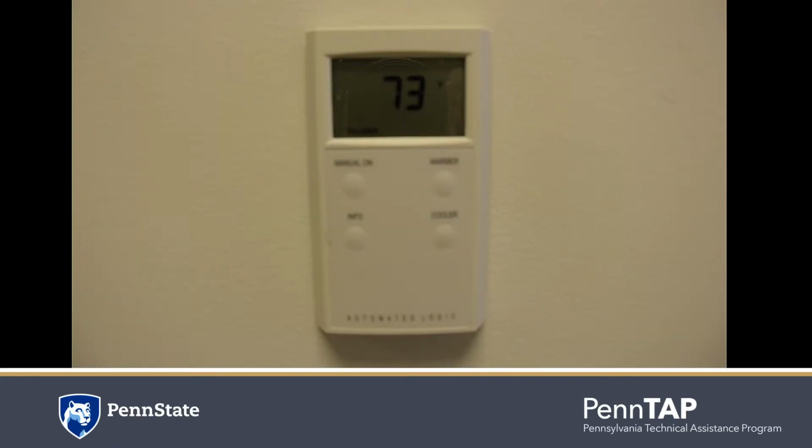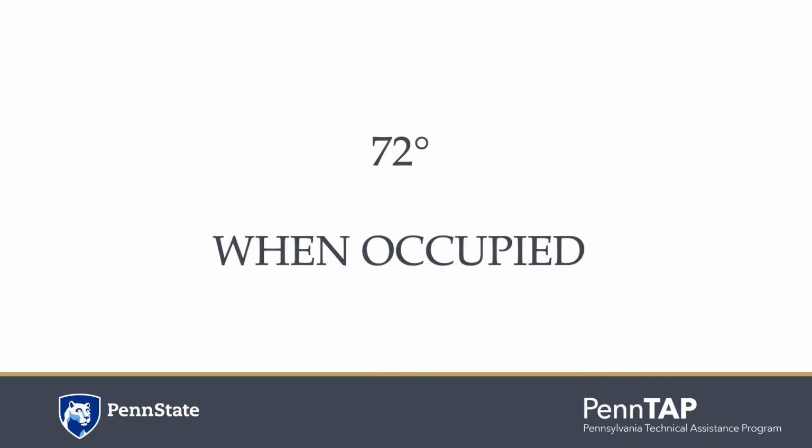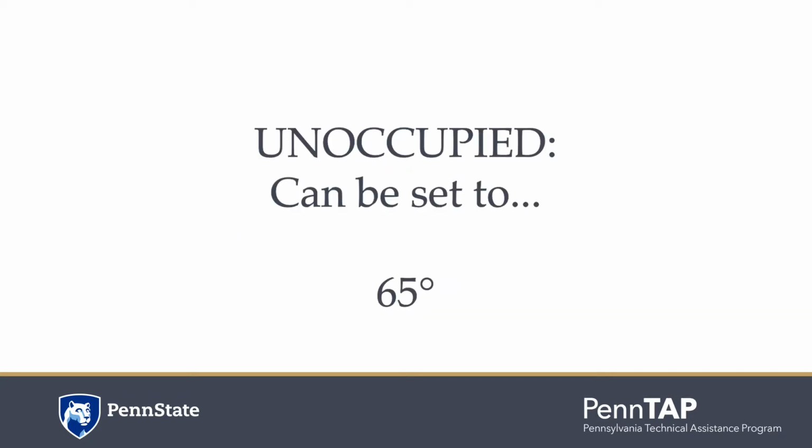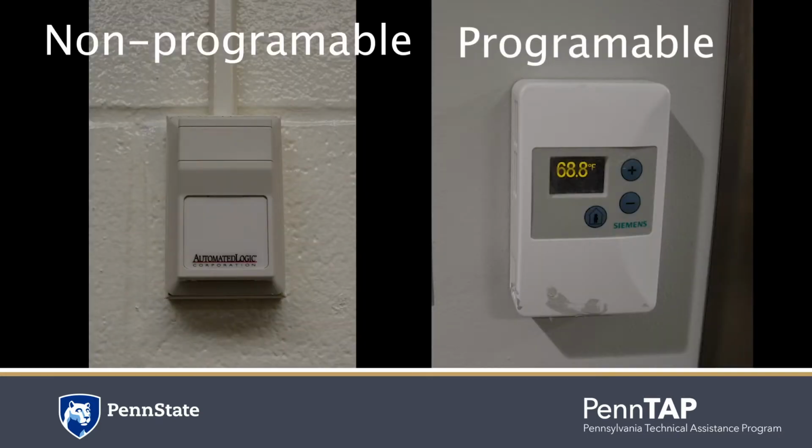Programmable thermostats are an easy solution to adjust the indoor ambient temperature. Set the indoor temperature at 72 degrees when occupied. Unoccupied buildings can be programmed for lower temperatures in winters to 65 degrees Fahrenheit. Since most days have the lowest temperature overnight when the building is unoccupied, a programmable thermostat limits the operation during the coldest time of the day.